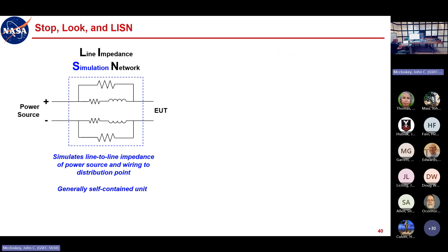A line impedance stabilization network is intended to provide a stable line-to-chassis impedance of the power source and the wiring to the distribution point. The high frequency, in this case 50 ohm shunt impedance, is provided by the input of the measurement receiver. So these stabilization networks generally have an RF port that you connect a 50 ohm cable to, which goes to the 50 ohm input of a measurement device.